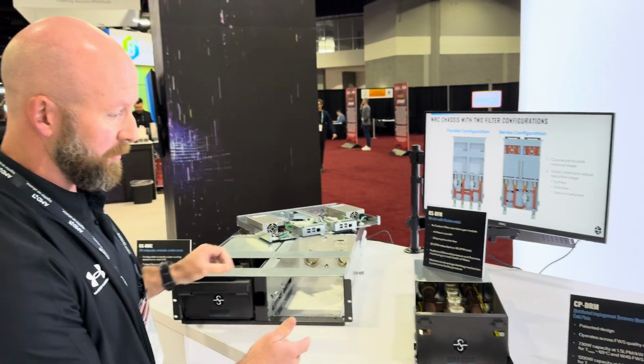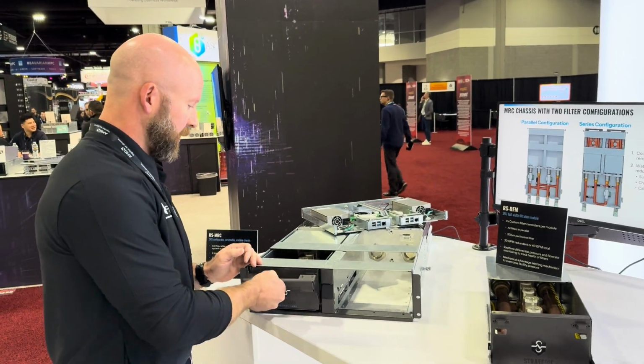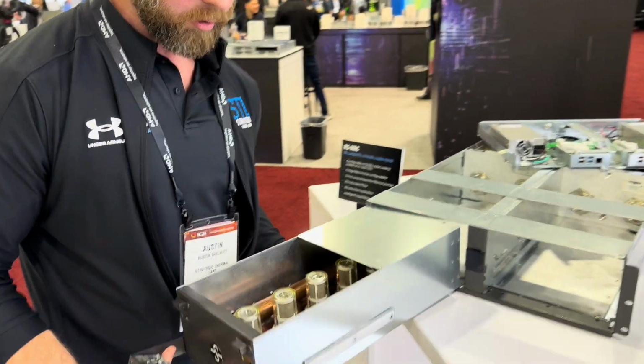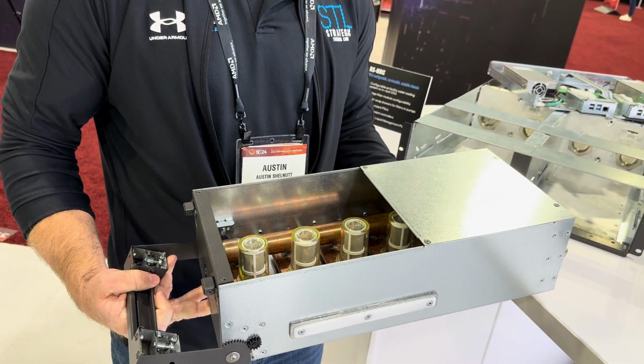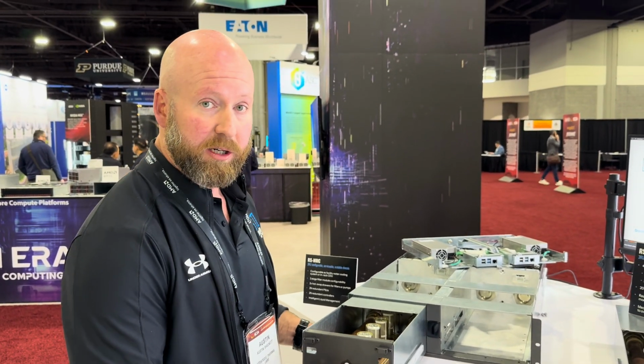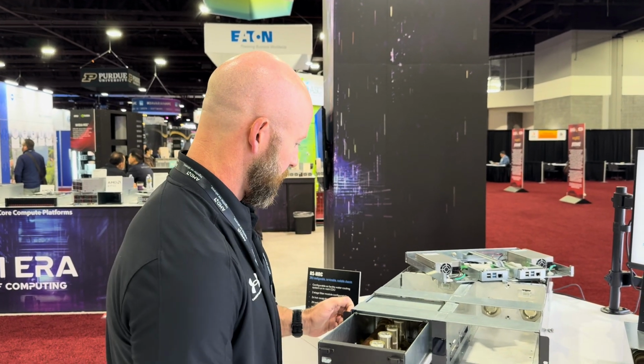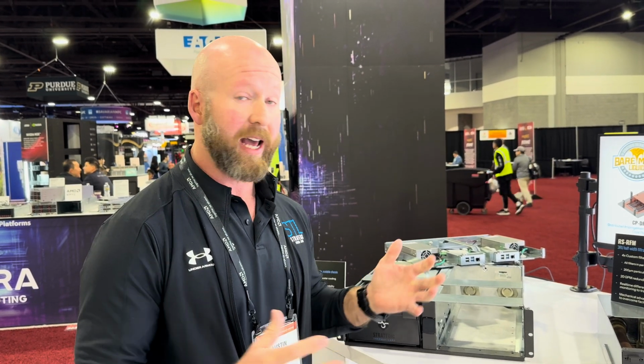Just to my left here, this is the same chassis that we use for our pump module and the same hot pluggable drawer, but for a bare metal installation, we replace the pumps with a filtration unit. Inside of each drawer, we've got very simple water filters, and these are 200 micron stainless steel mesh screen filters to gather out any residual particles that might possibly be in the water supply provided by the building. One of those filter trays has got differential pressure monitoring across the tray and flow meters so that we can create a relationship for flow impedance versus flow rate, and send out alerts to a building to let them know if their filters are getting plugged over time.